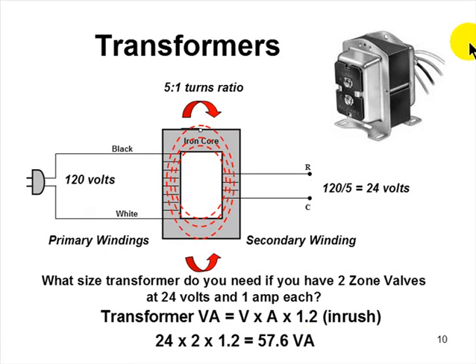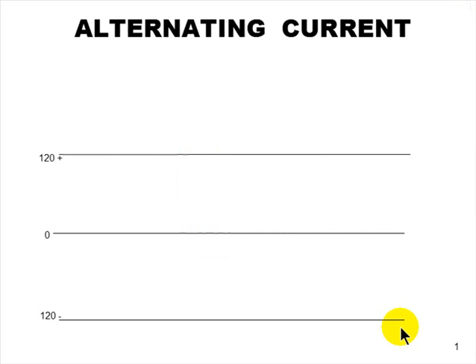So run out to the truck. Don't pick the 40 VA transformer. It ain't going to work. You know when it ain't going to work? When both valves are trying to open at the same time. Because then you've got a 2 amp load on that 40 VA transformer, and you need a 57.6 VA transformer. So go find that 57.6 VA transformer and bring it back. Good luck finding it.